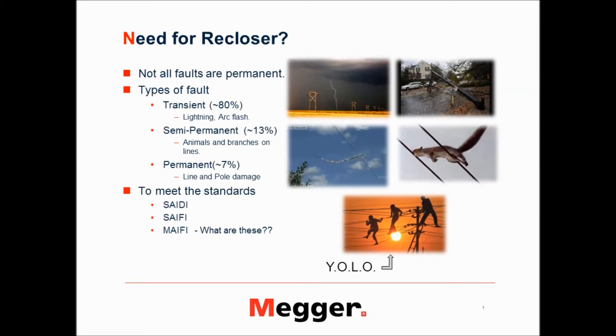Now we are going to move to why we need reclosers in your system. When we talk about faults, not all faults are damaging or permanent. Some are transient faults. As you can see in this slide, almost 80% of the faults that occur in our system are transient faults, which are only there for a couple of cycles or a couple of seconds and then disappear — like lightning or arc flash or something like that.